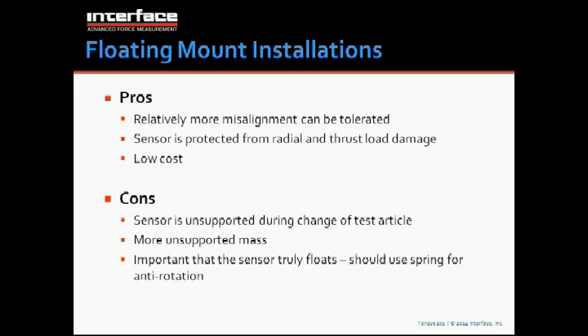Pros, like I said, relatively more misalignment. The sensor is protected from radial and thrust load damage. Imagine you can't really ruin the bearings by applying radial loads if you float the sensor in the middle of two flex couplings. Relatively lower cost. The sensors tend to be at least a little bit less expensive when you go floating mount style, and the couplings are less expensive because a single flex is typically going to be less expensive than a double flex style.